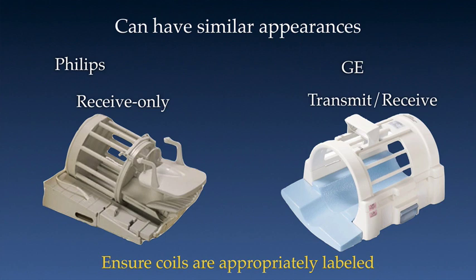It can be difficult to tell if a coil is transmit and receive or receive only simply by looking at it. As you can see here, depending on the vendor, they can have very similar appearances. On the left is a receive-only coil, and on the right is a transmit and receive coil. For safety purposes, it is very important to ensure that the coils are appropriately and properly labeled so that everyone knows whether they are using a receive-only coil or a transmit and receive coil. Some devices have conditions of use that specify a certain type of coil, so it is very important that they are very clearly labeled.